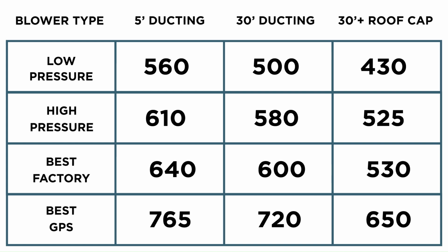And then you noticed as we took off the roof cap and the additional ducting, that hood went from 650 CFM up to almost 750 CFM. The IQ6 is actually an 800 max CFM blower, meaning that wide open, it could perform at 800 CFM. It's all about having those additional profiles above 600 that allow the hood to calibrate to the trickier installation, to compensate for the 90-degree elbow, for the extra long duct run. It's all about locking in at that 600 or 1200 CFM performance.